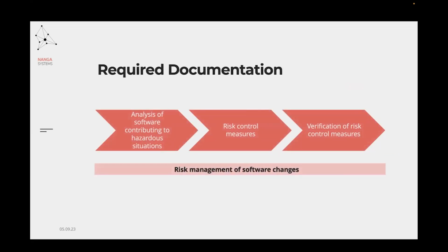The software risk management documentation requirements are defined in IEC 62304. There are three main activities: analysis of software contributing to hazardous situation, risk control measures, documentation of risk control measures, documentation of verification of risk control measures. And risk management activities should be continuous throughout the project lifecycle to include risk management, for example, of software changes.